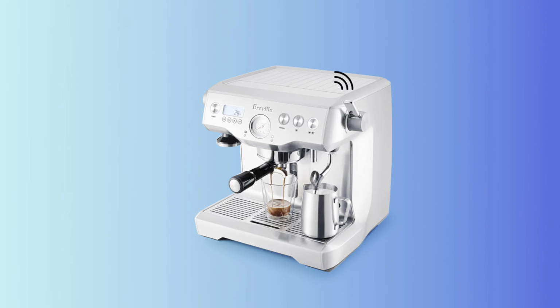The most common sign of leaking O-rings is usually a hissing sound. You can usually hear this on the top right hand side, where the top of the steam boiler is, and these are the most common O-rings to fail, because they work under a much higher temperature than the others.